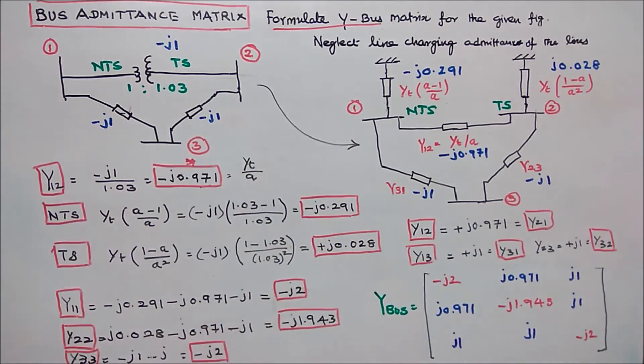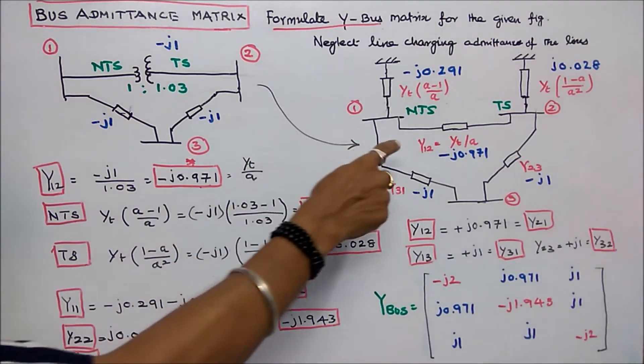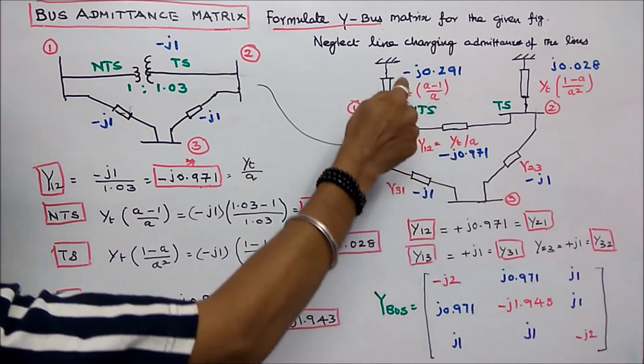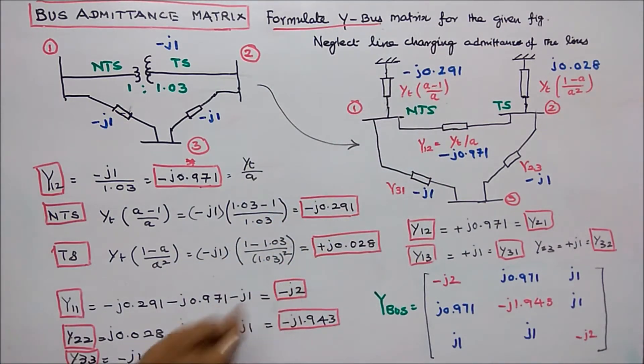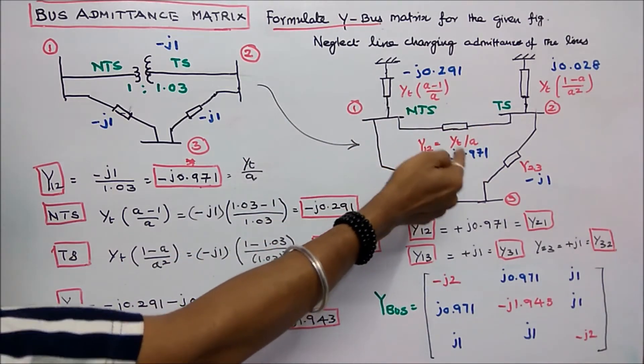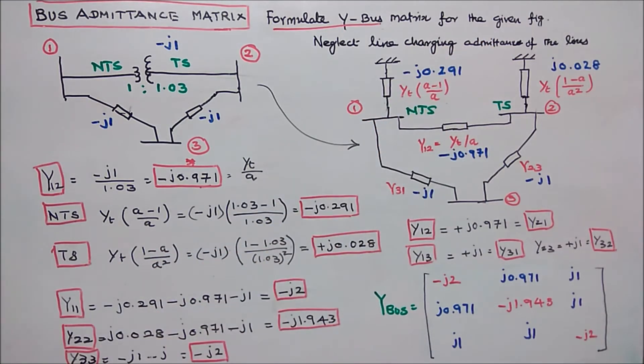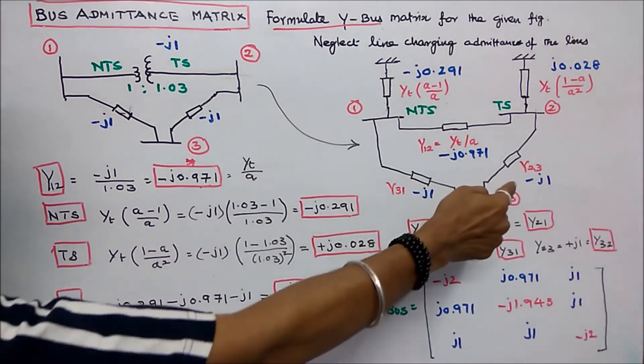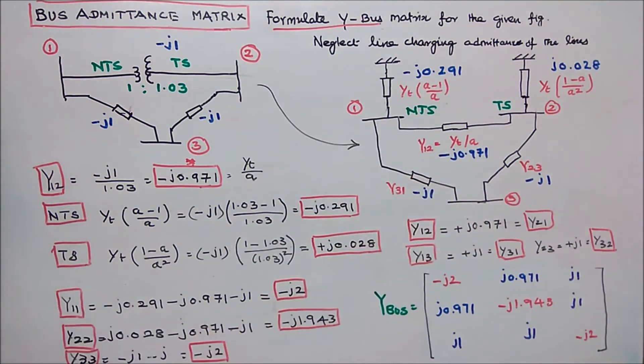Third step: we have to form the Y-bus matrix. First, Y11: three elements are connected, so Y11 equals minus J0.971 minus J0.291 minus J1, which equals minus J2. Y22 equals minus J0.971 plus J0.028 minus J1, which equals minus J1.943. Y33 equals minus J1 minus J1, which equals minus J2. The diagonal elements are complete.